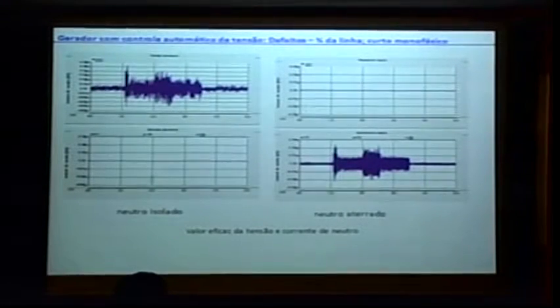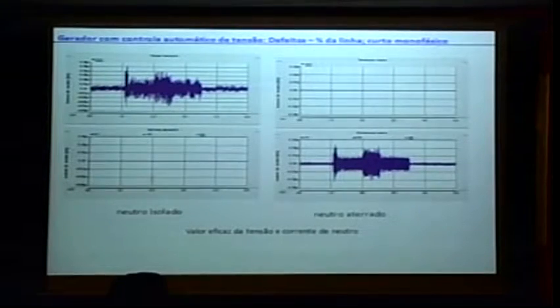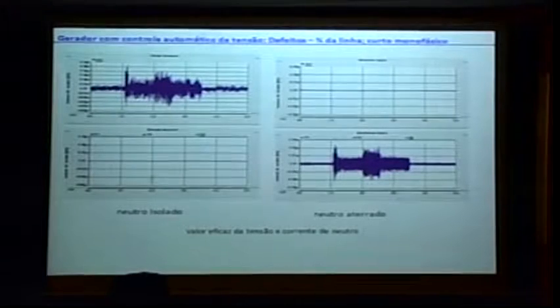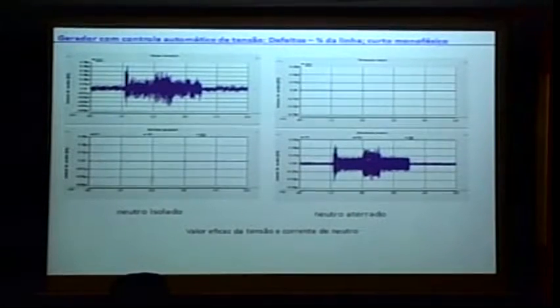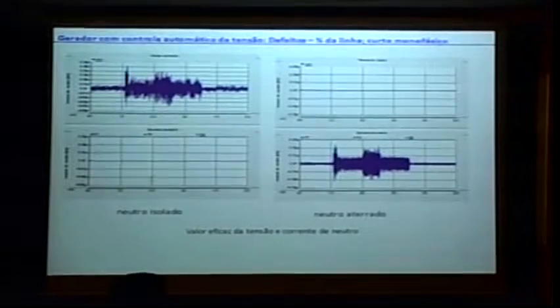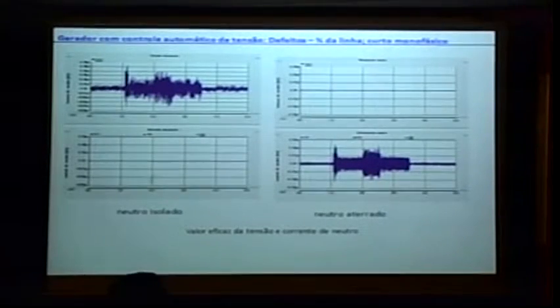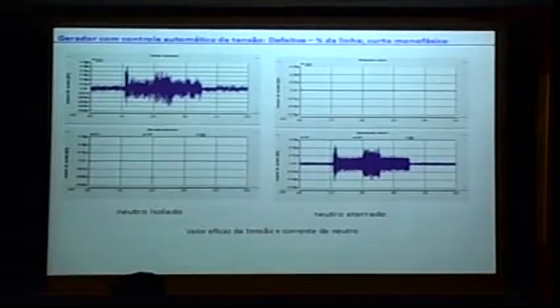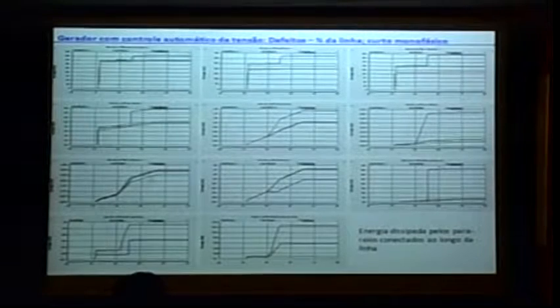The voltage profile is not equal in the three phases during short circuits. In case we have isolated neutral, you're going to have neutral voltage that will appear for the unbalanced short circuit, but it was low. With the solidly grounded neutral, it was the neutral current that appeared. Here the isolated neutral, here the grounded neutral, but it appeared low, perhaps not enough to detect a single-phase fault. Dissipated energy in the surge arresters: in the case of the single-phase short circuit at 3/4 of the line, there was no triggering of the gap. Only the surge arresters dissipated energy.